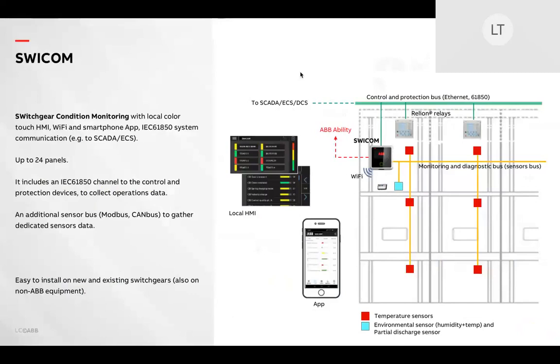Simple answer to that one is relays are mission critical to every organization, and they're also therefore protected. No one wants to inadvertently alter a setting on a relay that can affect adversely the operation of the plant. Additionally, SWICOM can be read remotely via an Android or Apple device, or local or remote HMI, and again, keeping personnel at a distance from the switchgear and keeping them out of harm. SWICOM's advanced analytics are not solely reliant on relay data or sensor data, but take into account many years of data ABB has collected on our assets in the field.